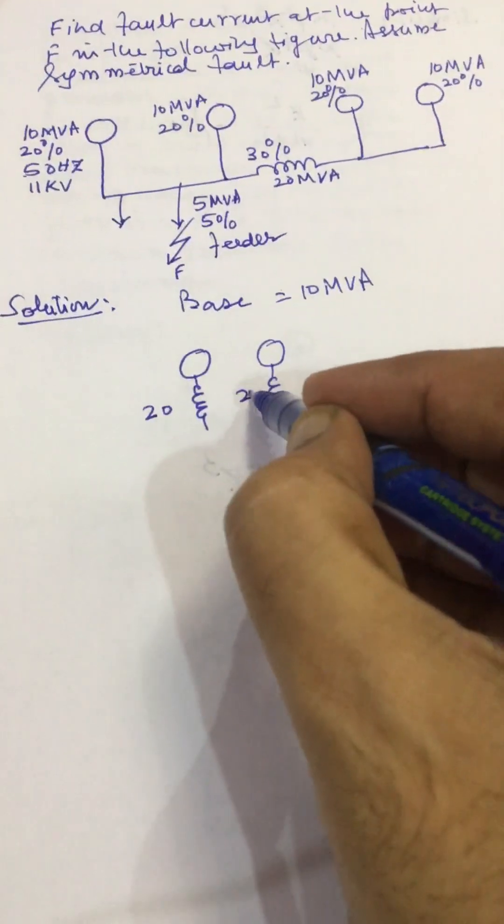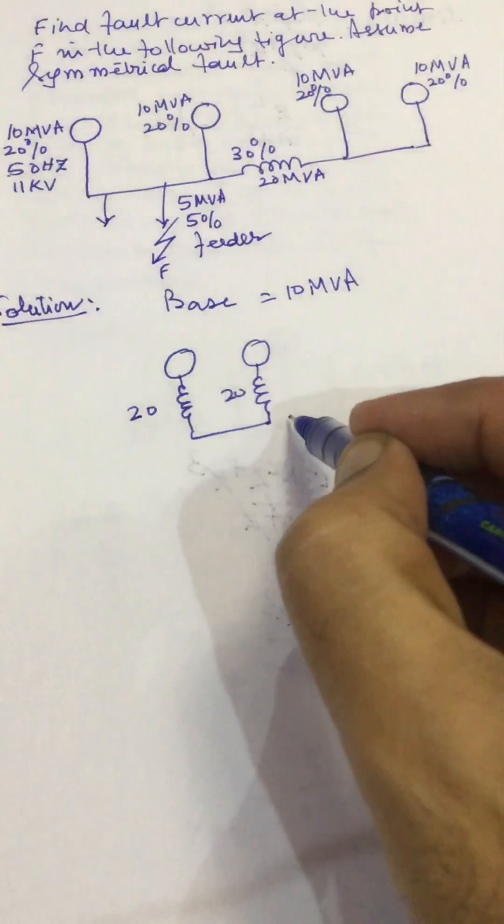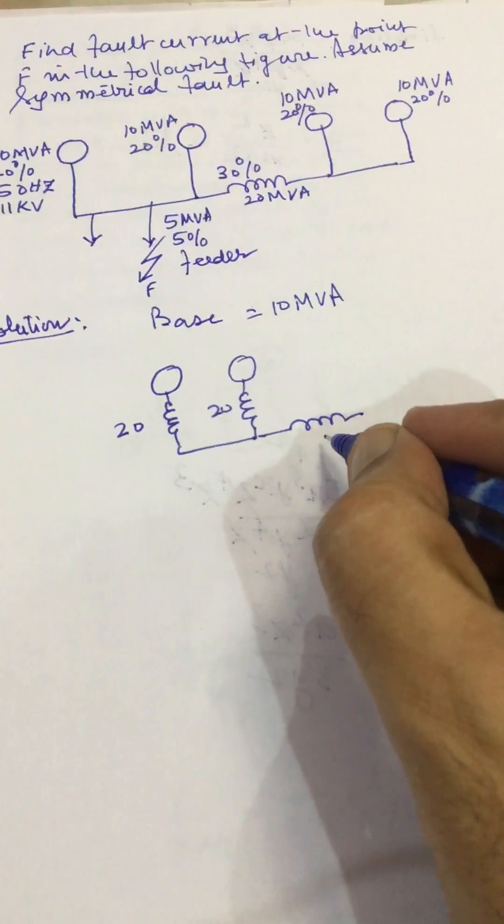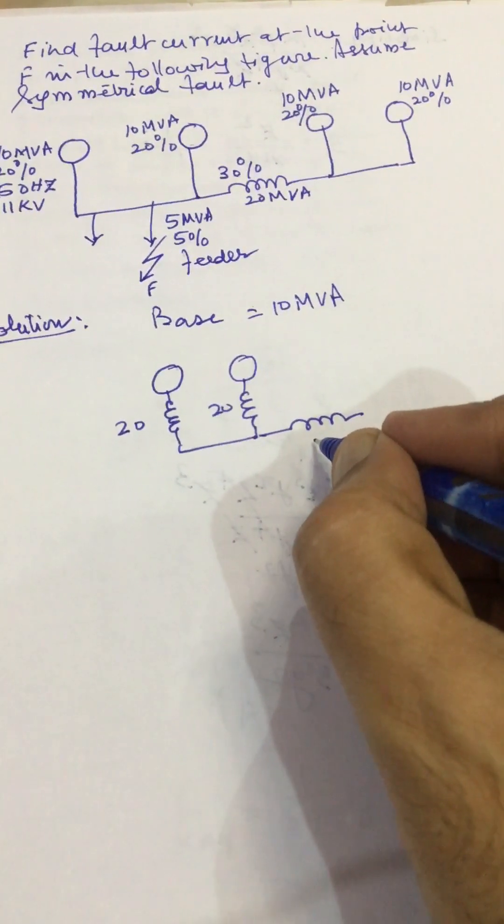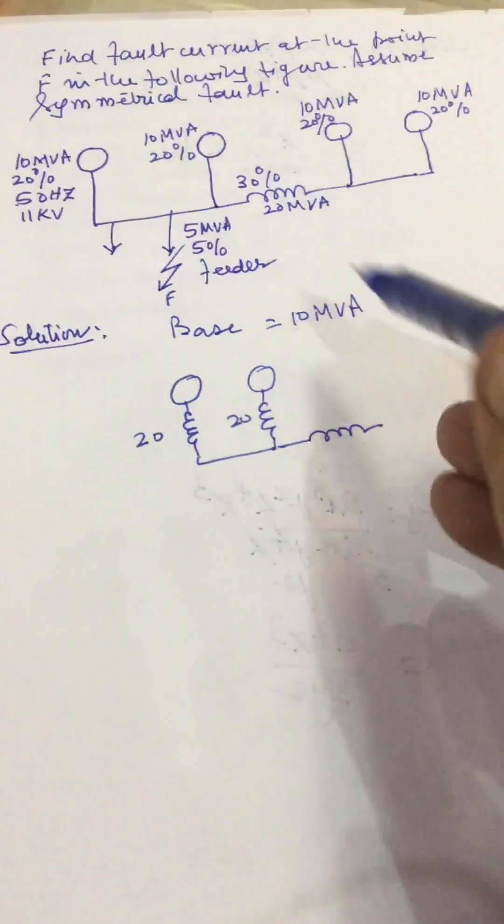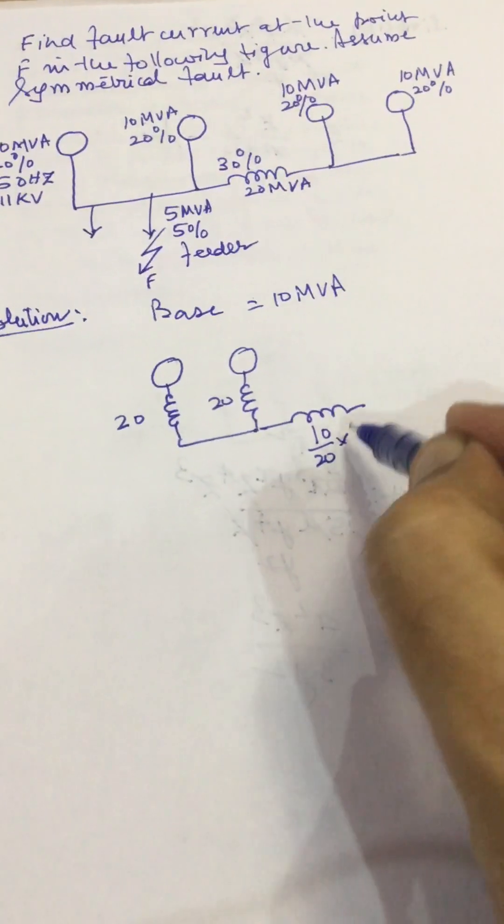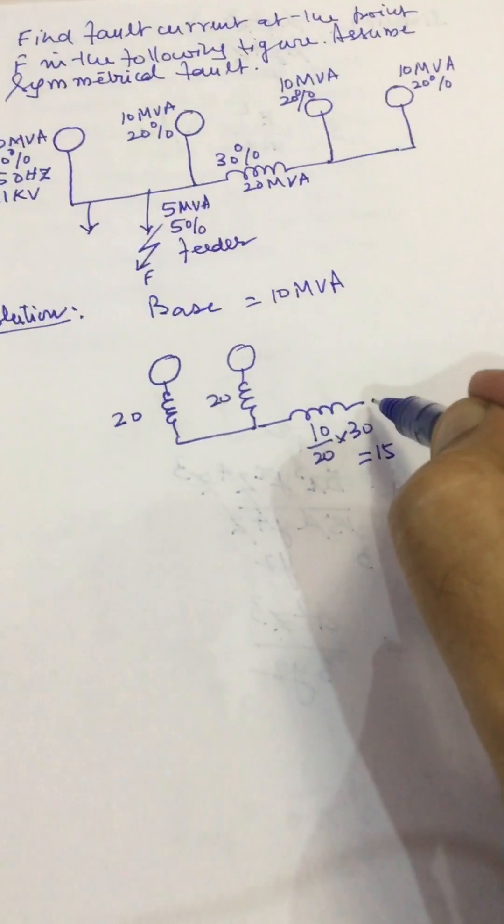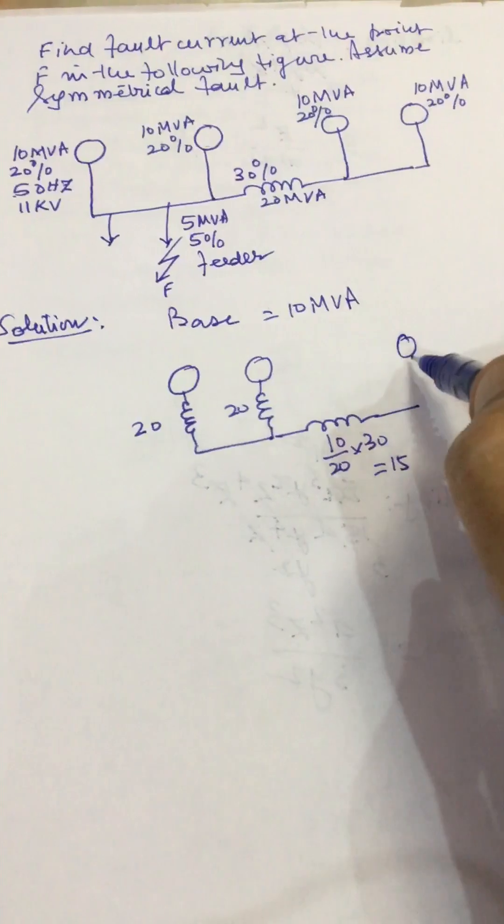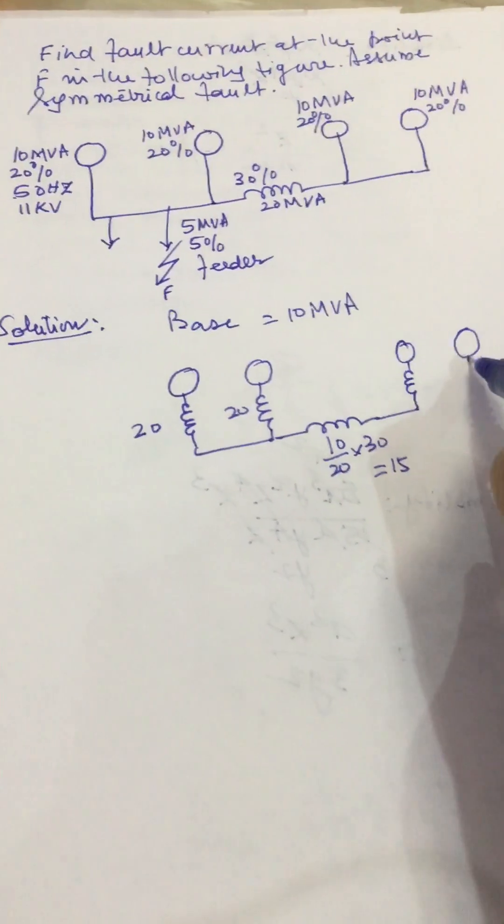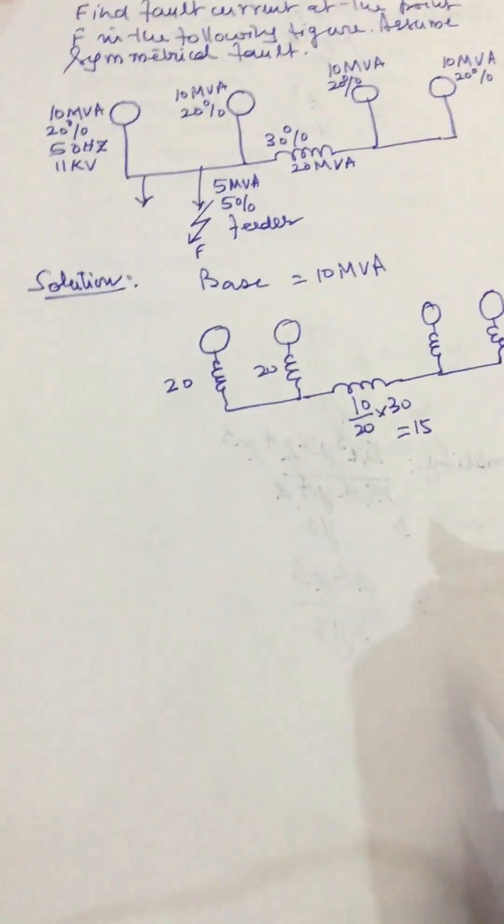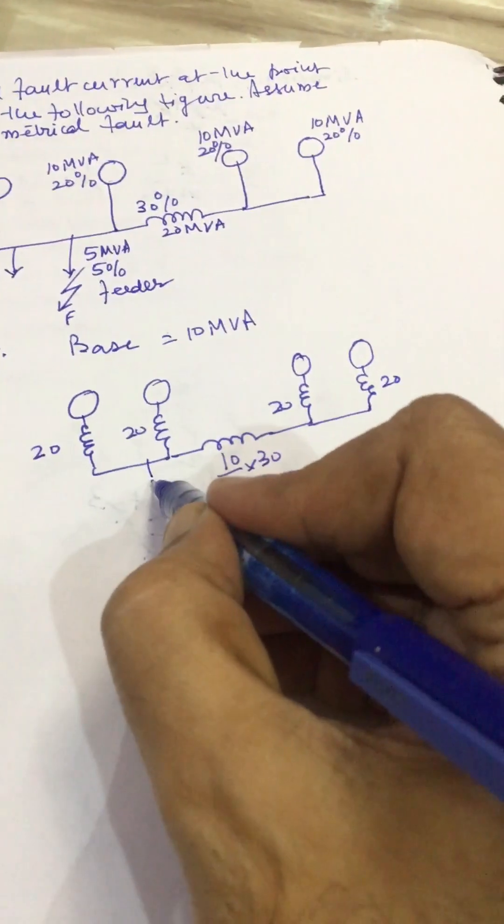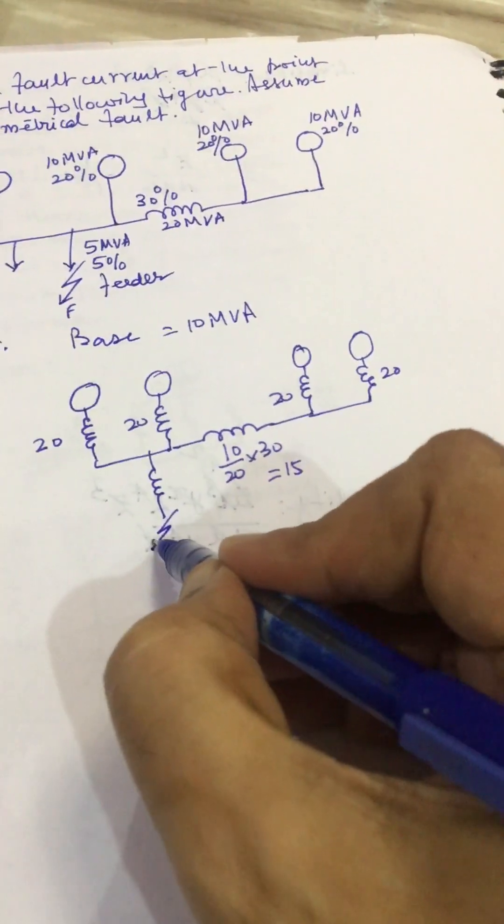This is 20 percent, this is 20 percent and this is 30 percent at 20 MVA. So this will be at 10 MVA, this is 30 percent, so this will be equal to 15 percent and these reactances will remain same, this is 20 percent and this fault takes place at this point.